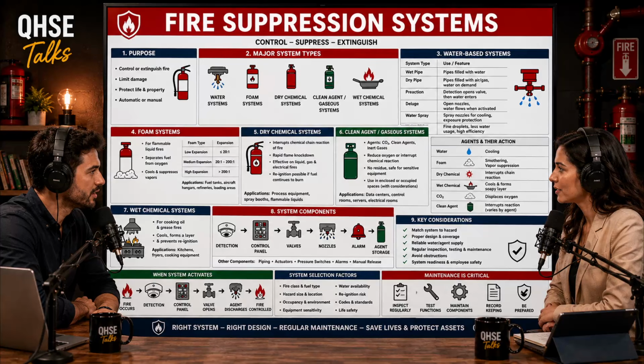You design a deluge system when the hazard is so volatile and the fire growth potential is so rapid that you simply cannot afford to wait 60 seconds for individual thermal heads to pop. Give me an example. Think about a massive aircraft hangar housing jets full of aviation fuel. If a fuel line ruptures and ignites, the fire can spread across a massive pool of jet fuel in milliseconds. Right. A deluge system acts as a massive instant water curtain. It suppresses the flames, prevents radiant heat from igniting adjacent aircraft, and cools the structural steel of the roof so it doesn't collapse. It's a brute force approach for extreme hazards.